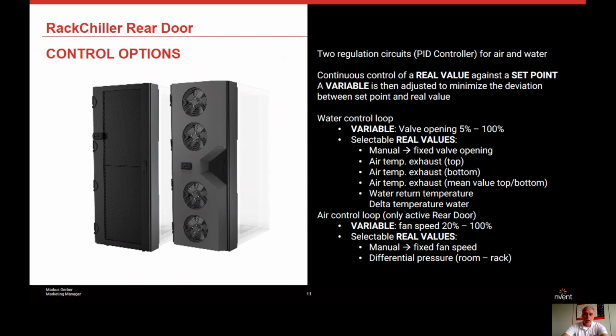And now coming back to my example, if one of the doors would fail, the room would not heat up because the other ones regulate on this 22 degrees. So they will take over, and there is no risk or very, very small risk that your equipment is overheating. What can happen is, because the air has to be moved by the equipment, that there is an air resistance with the coil.